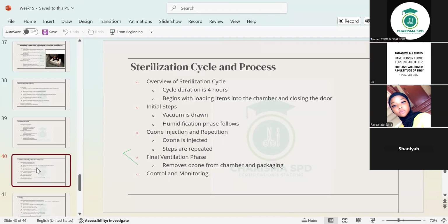So you see the first cycle of the loading and then the vacuum drawn and the humidification phase. If the humidification is not up to the percentage that it wants, that's where it's going to abort this load. And aborting the load is about canceling the load. We say it's aborted. So it's going to reverse everything, and then you have to take the instruments out again and reprocess. All right? So these are the steps that it is going to go through.